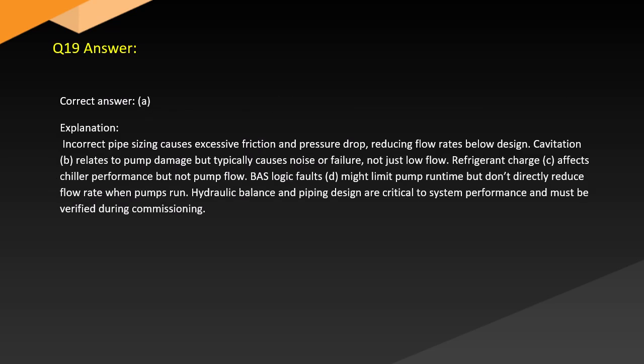Answer. Correct answer. A. Explanation. Incorrect pipe sizing causes excessive friction and pressure drop, reducing flow rates below design. Cavitation, B, relates to pump damage but typically causes noise or failure, not just low flow. Refrigerant charge, C, affects chiller performance but not pump flow. BAS logic faults, D, might limit pump runtime but don't directly reduce flow rate when pumps run. Hydraulic balance and piping design are critical to system performance and must be verified during commissioning.